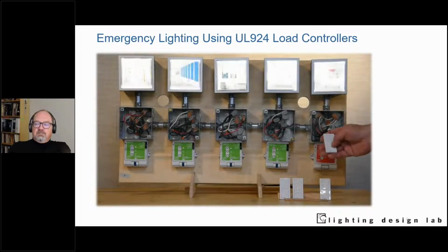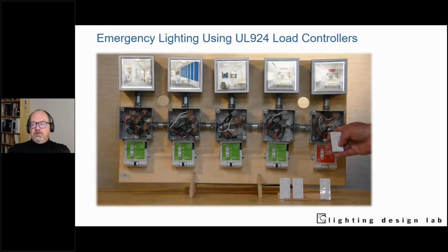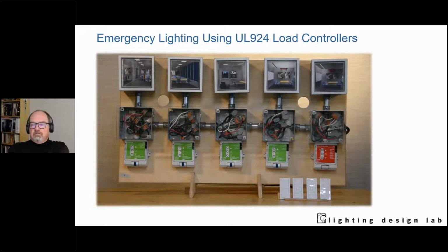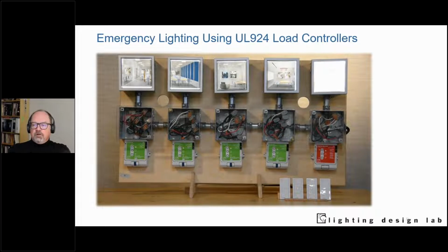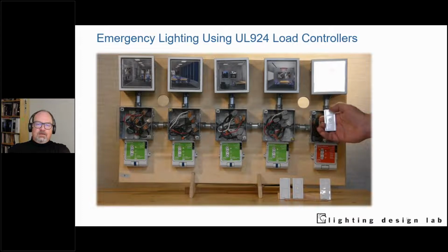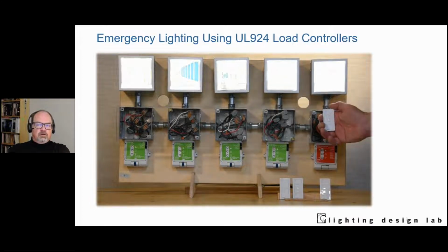So again, this is the demonstration board I showed you. I've just turned on all the lights, and I'm dimming all the lights, so I have complete control there. Now I'm going to turn off the power to it for a second. This isn't quite as obvious as the other demonstration, apologies. But you'll notice that when the power is restored, that emergency zone is at full brightness, not the dimmed level, and you can't turn it off for a certain period of time.